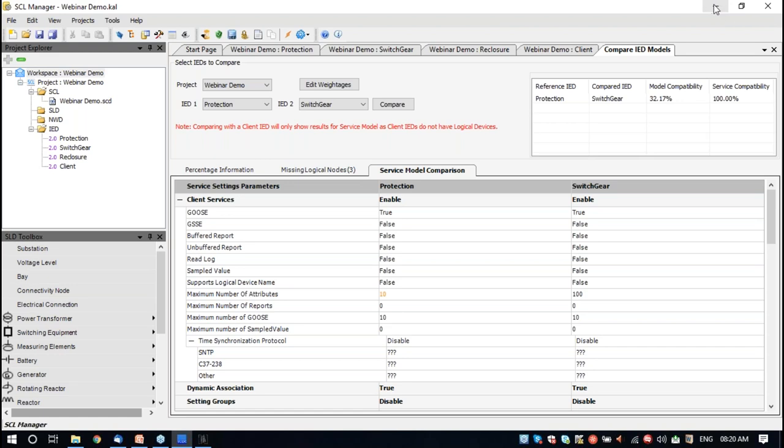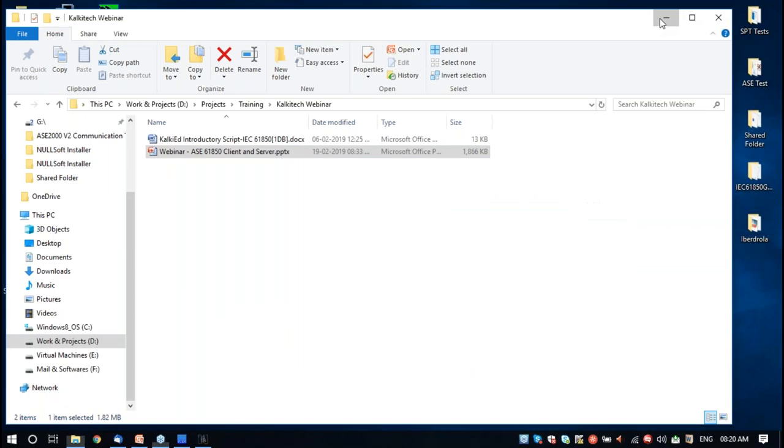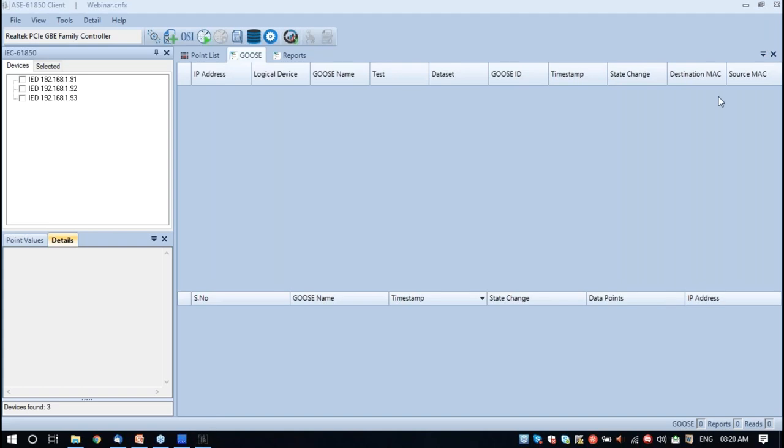I will switch to the live demo at this point. With this I am winding up the SCL Manager part. Now I will switch to the other function — the server. To give an overview again, this server will have three alias IPs. It will have the protection function, the switchgear function, and the reclosure function loaded into it. The client will be simulated in the same laptop. The idea is to have three alias IPs and run three servers at the same time in the demo.